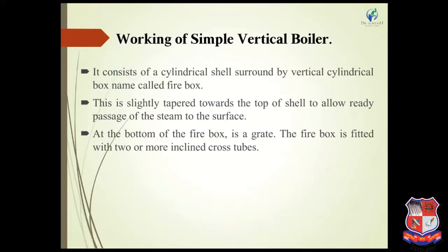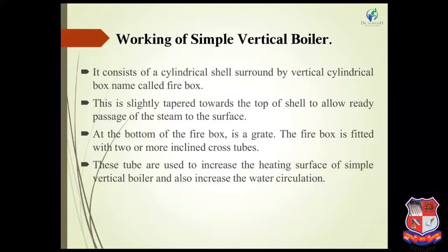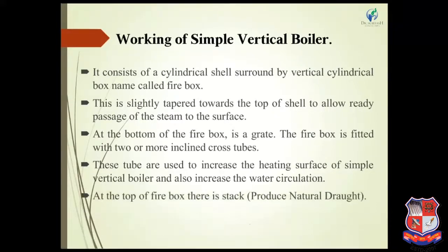In the firebox, two or more tubes are inclined because we have to give a higher heat transfer rate by increasing the surface area. These tubes are used to increase the heating surface of the simple vertical boiler and also increase the water circulation. At the top of the firebox there is a stack to produce a natural draft.